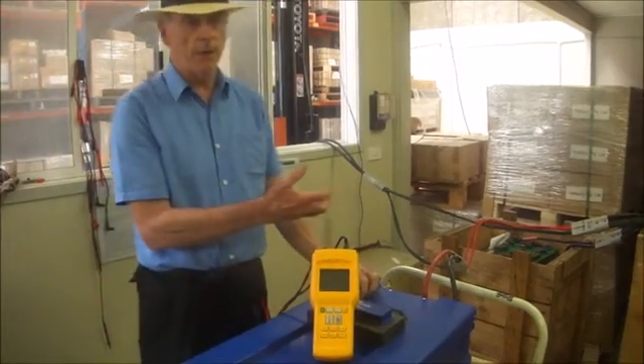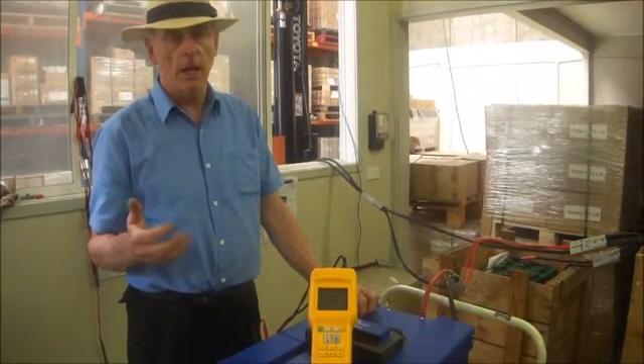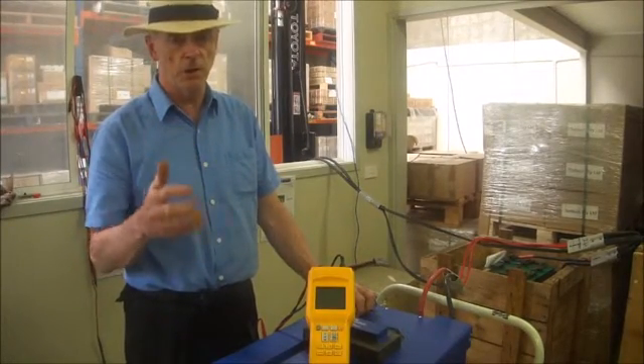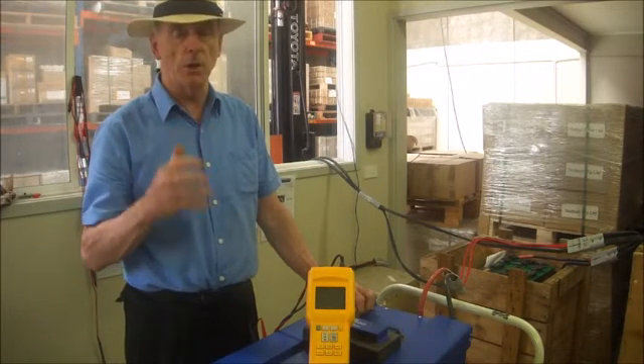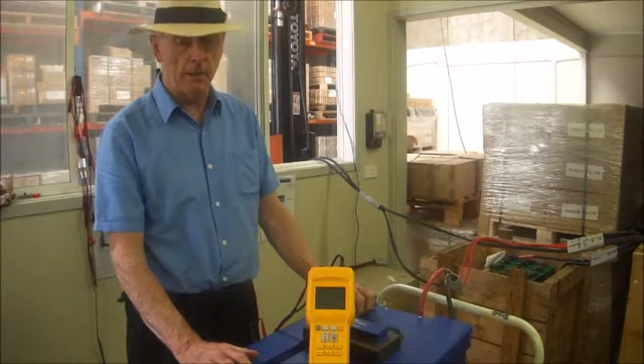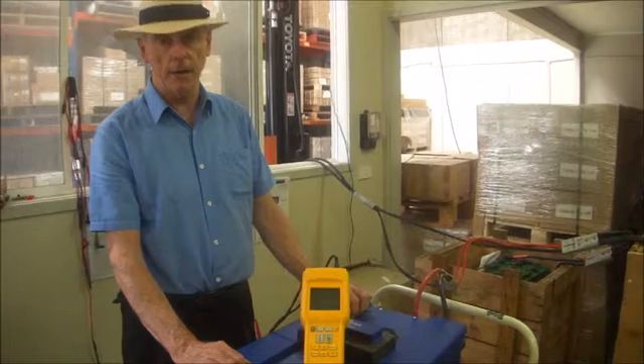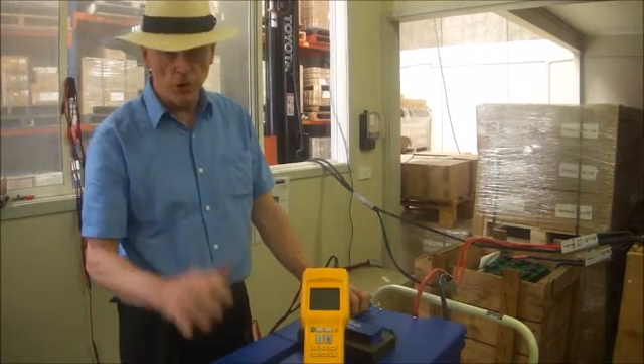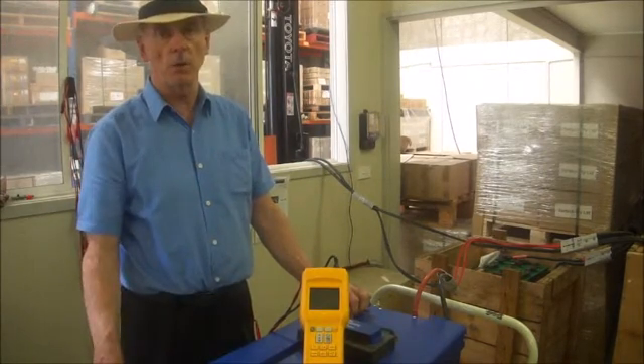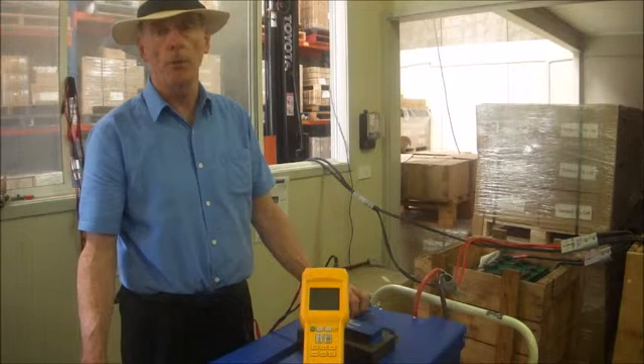The amount of power that a load absorbs is only really dependent upon the 50 Hertz component. So if we're drawing out of the inverter a lot of harmonics or multiple harmonics, that power at that harmonic, which is the 100 Hertz, the 150 Hertz, 250 Hertz, 200 Hertz, that power is unusable, in particular when it comes to a reactive load like a motor. So the useful power that comes out of the inverter, we want to make it as identical as it comes out of the power point of your house. That means we want to reduce the total harmonic distortion, reduce the harmonics, and maximize the fundamental component.